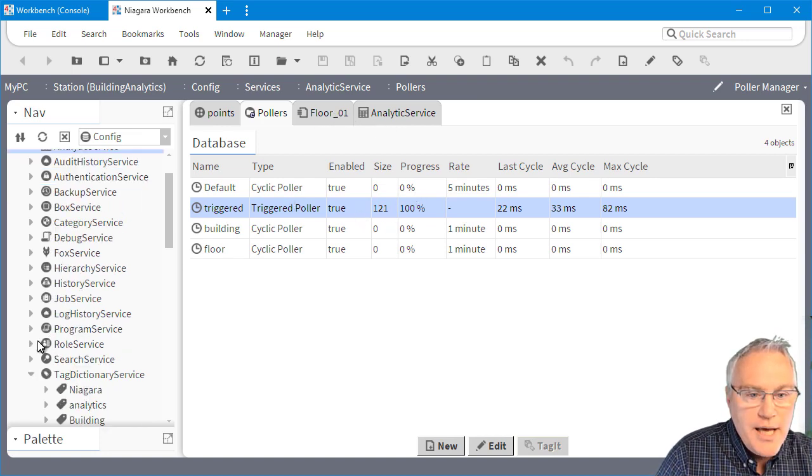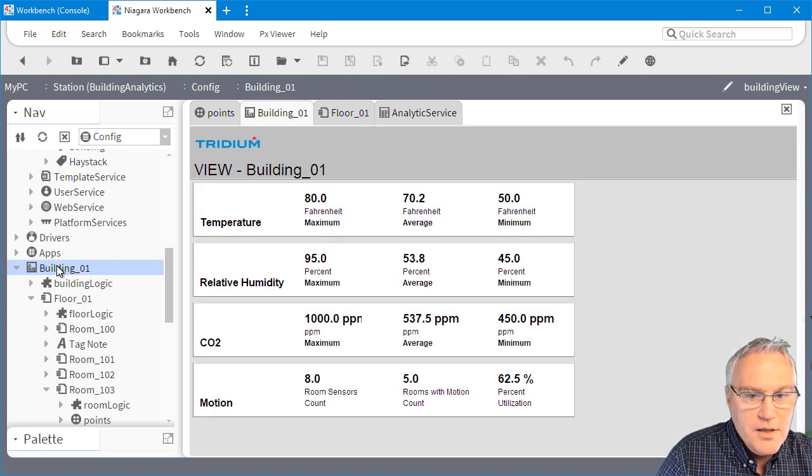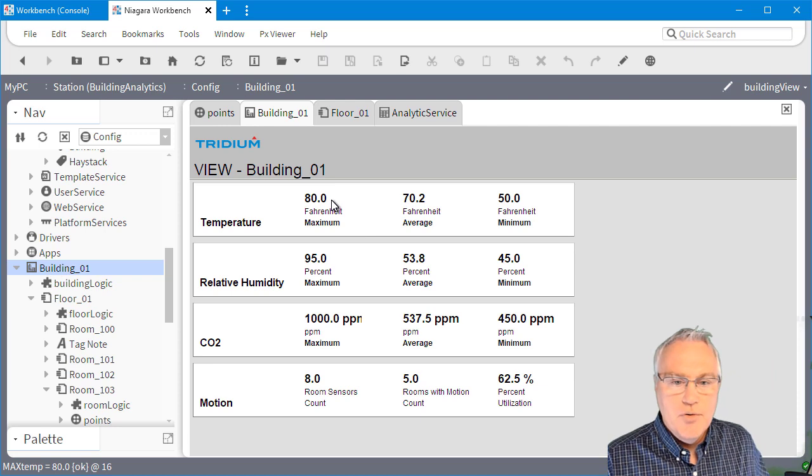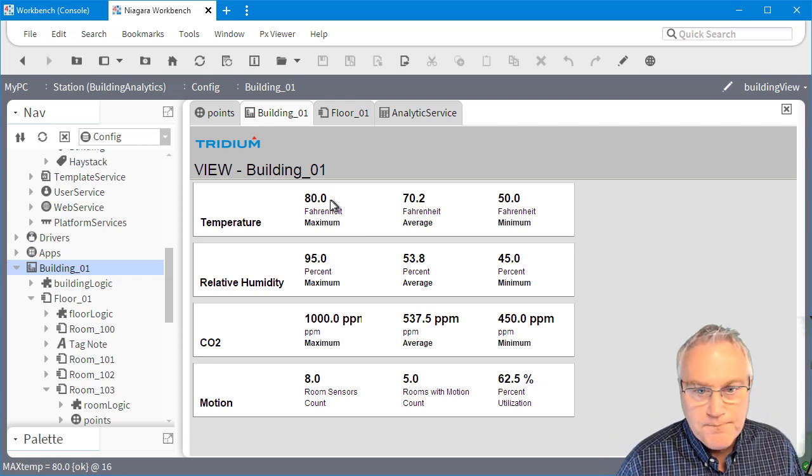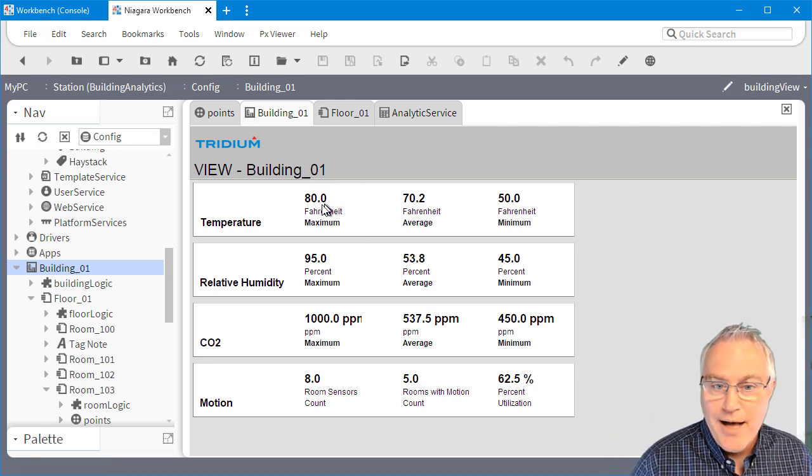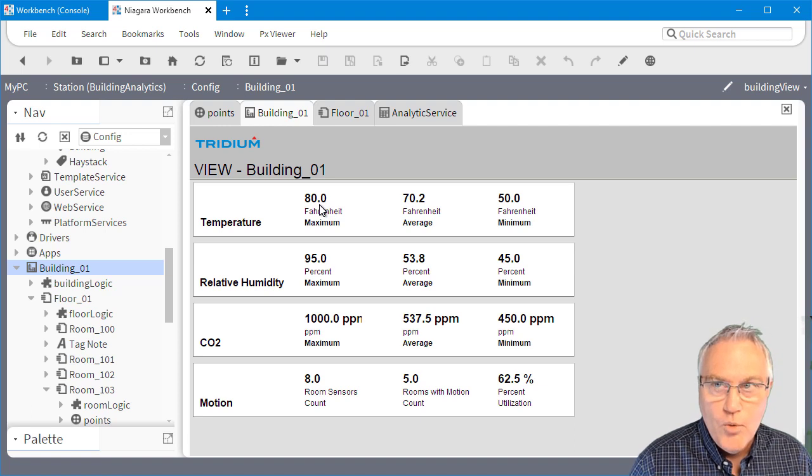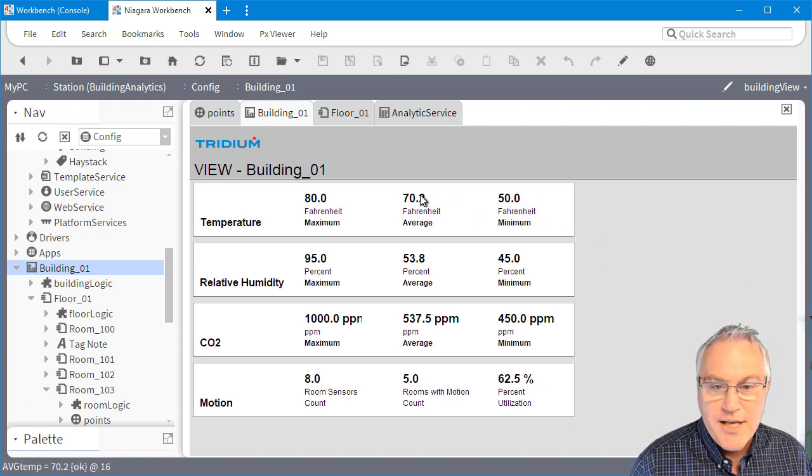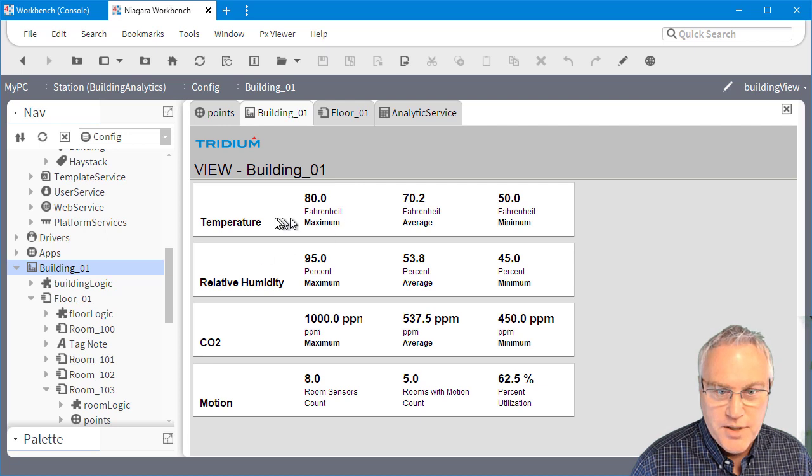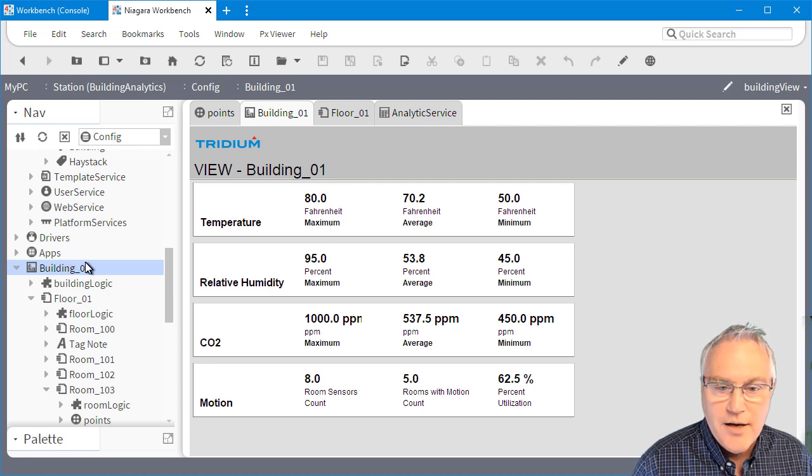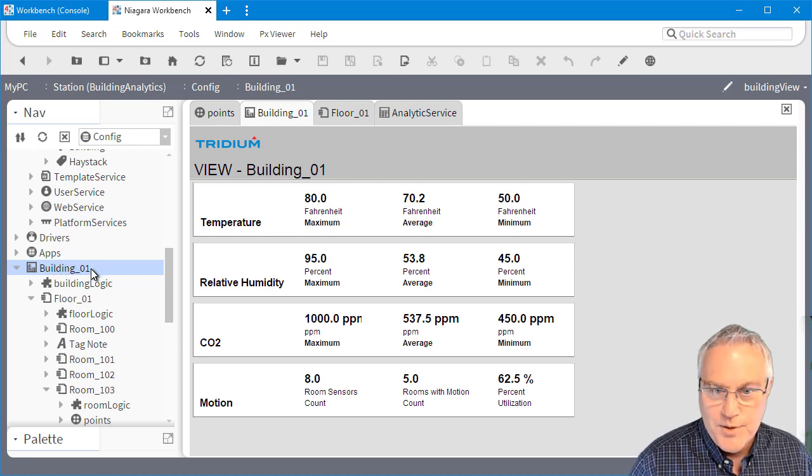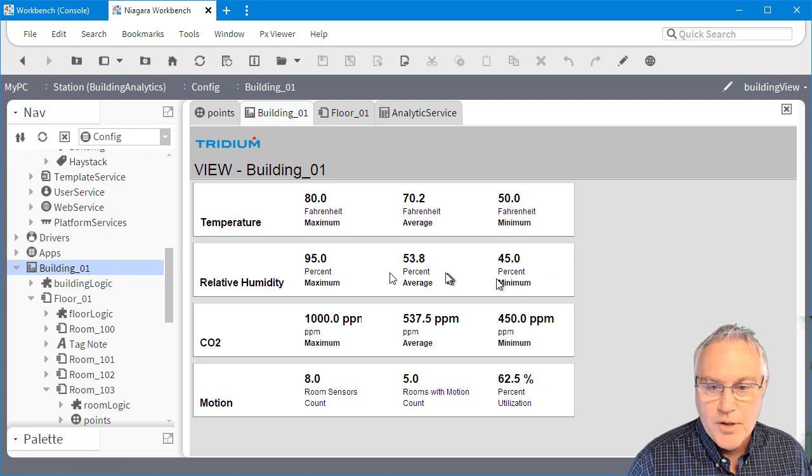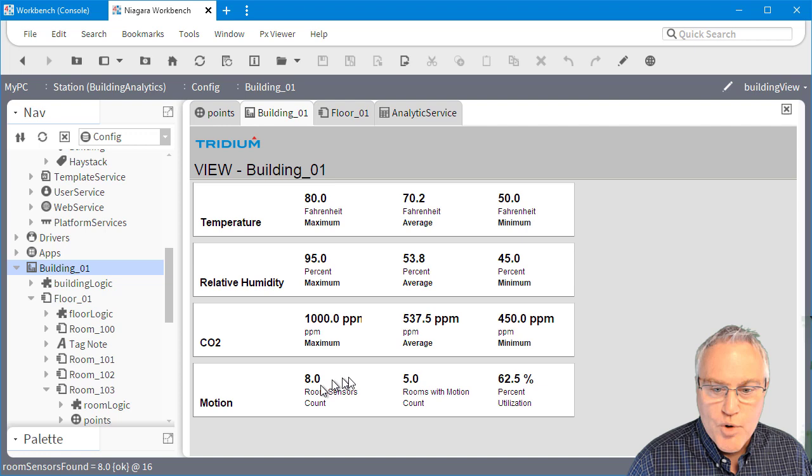So now if I go down into, and we'll just use the interface that I put on there, you'll see that at the building level, we get the 80 degree. So it found that on floor one. And it found the minimum on floor two. And it gave us the average of all the temperatures. So it's evaluating at the building level all of the rooms and all of the floors. Same thing for relative humidity and the parts per million.